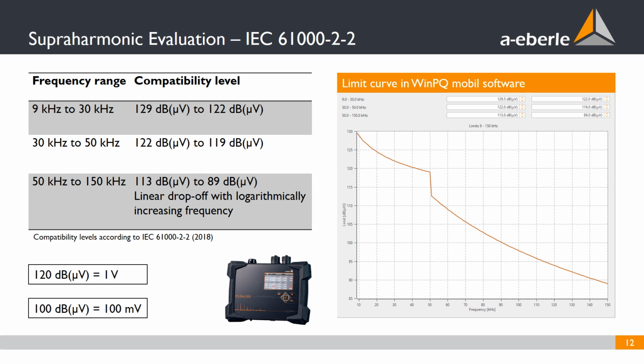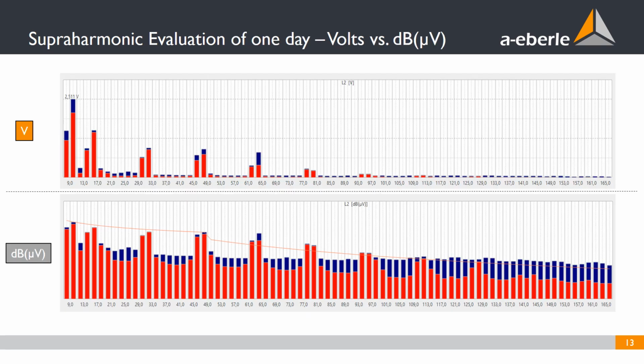And now if we take the PQ-Box 300 and make a measurement for 1 day, it is possible to make a statistical evaluation of the charging processes, and this is what you can see here. This is a bar diagram. The red bars show the 95% value, meaning 95% of the values were lower than this, and the blue bar shows the maximum value. In the top diagram, you can see these values in volts. So this was about 2.5 volts maximum. As you remember from the snapshot before, we had about 1.5 volts. So there was a time where this disturbance level was a little bit higher.